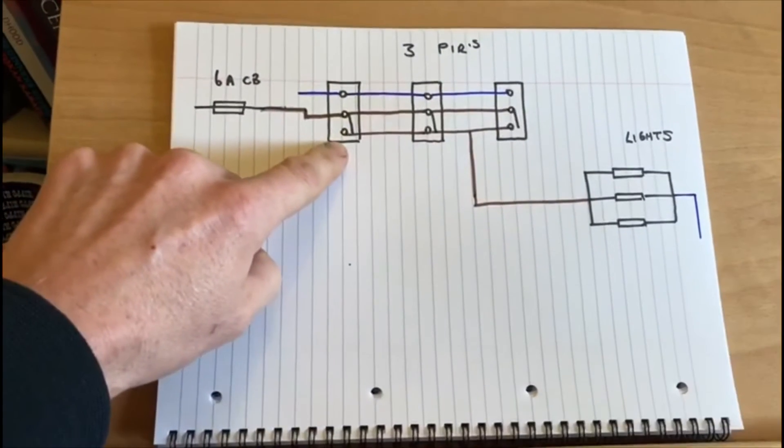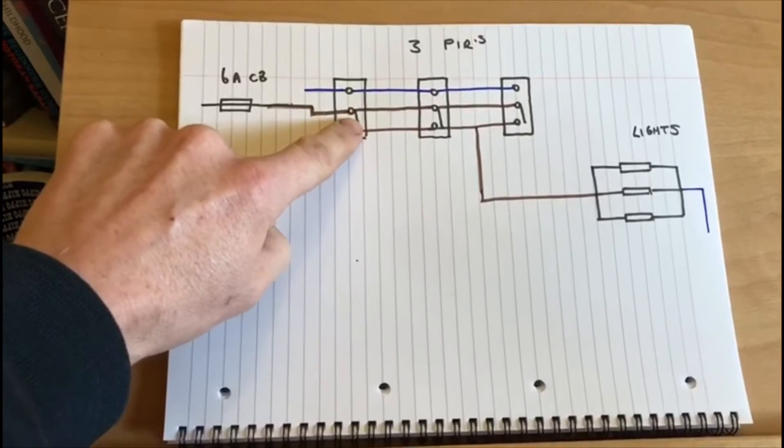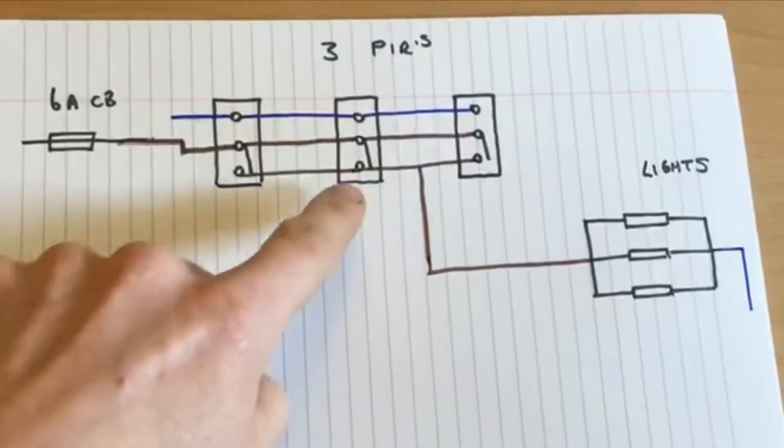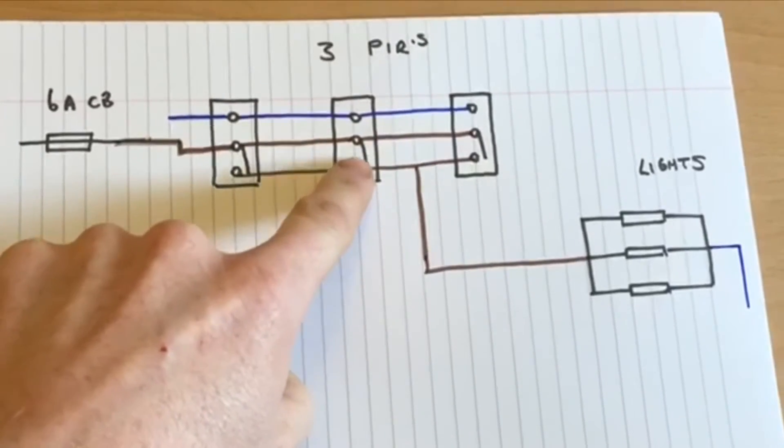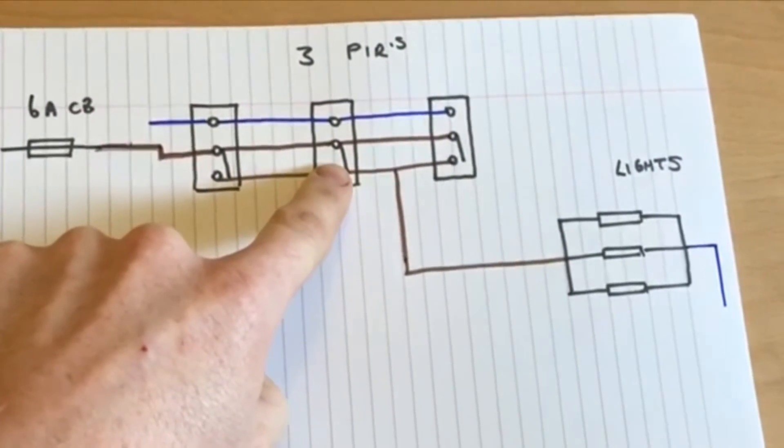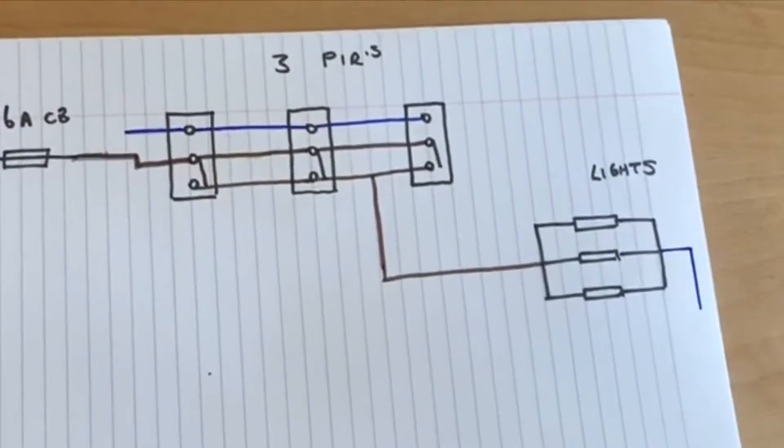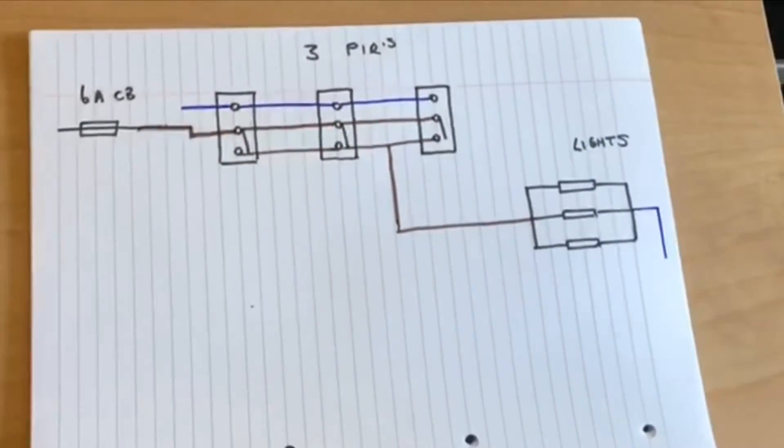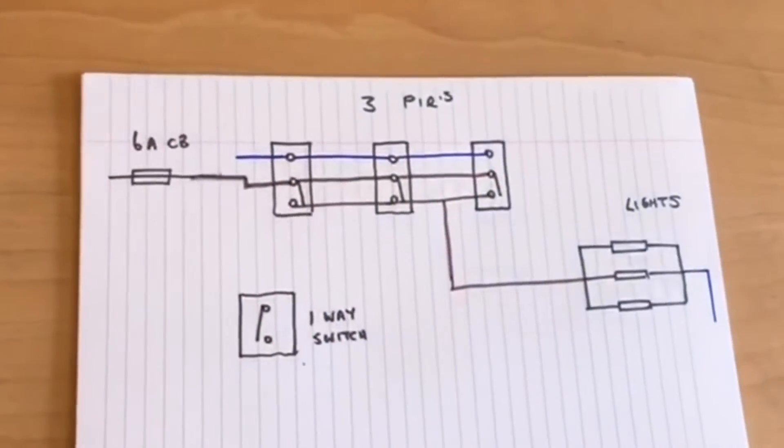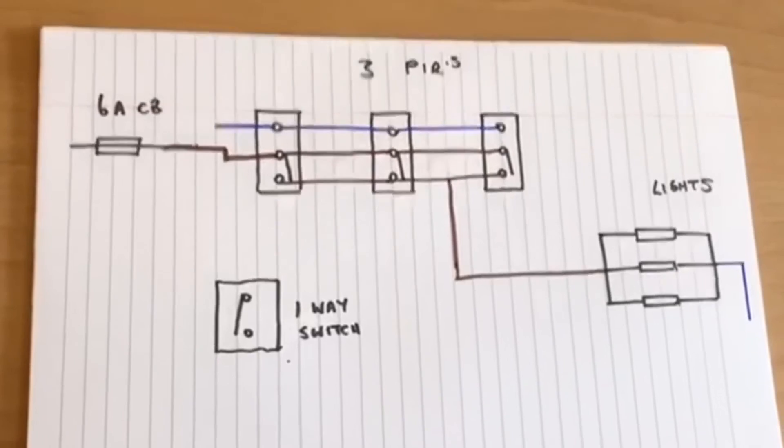All three PIRs are now controlling those lights. It's a good idea to have the times all set to about the same sort of time, although it doesn't really matter. This one could be set at a different time. So if this one was set on say 10 seconds and this one went off, it would only last for 10 seconds. Whereas if this one was to go and that was operated for two minutes, then this one would operate the lights for two minutes until the timer runs out on that one.